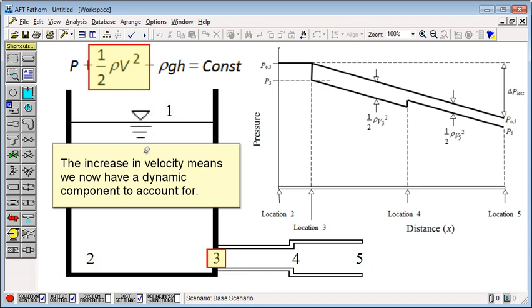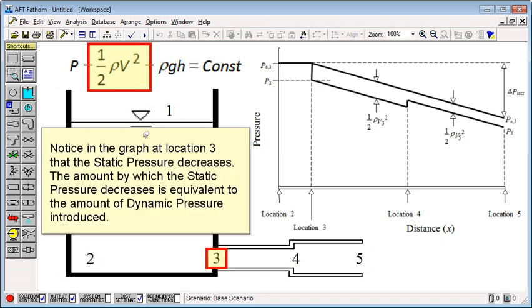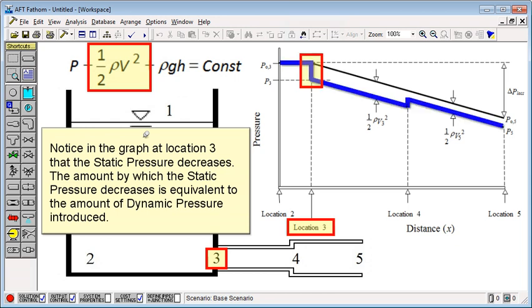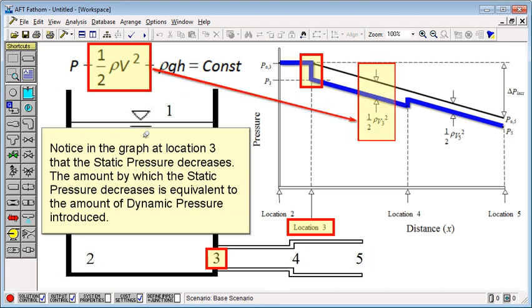The increase in velocity means we now have a dynamic component to account for. Notice in the graph at location 3 that the static pressure decreases. The amount by which the static pressure decreases is equivalent to the amount of dynamic pressure introduced.